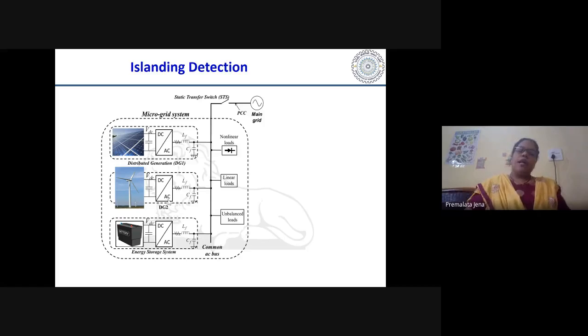Somebody may ask you why, in unintentional islanding, we are so much interested in shutting down the DG. What is the need? Because suppose at this bus you have some loads present on the grid side, and suddenly the grid is off, but those customers, the line person, will come to the grid that is off, but still the load is getting power from the renewable side.